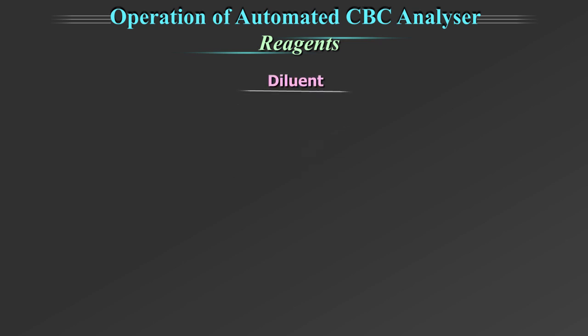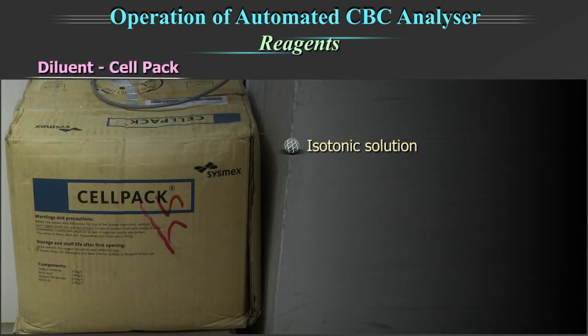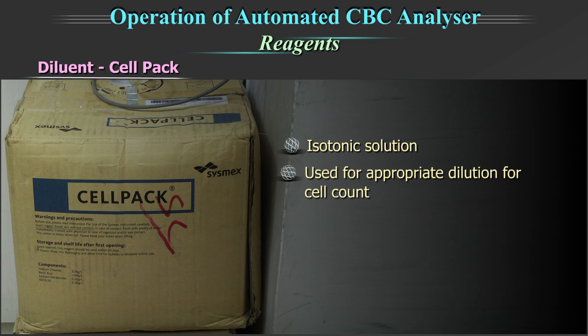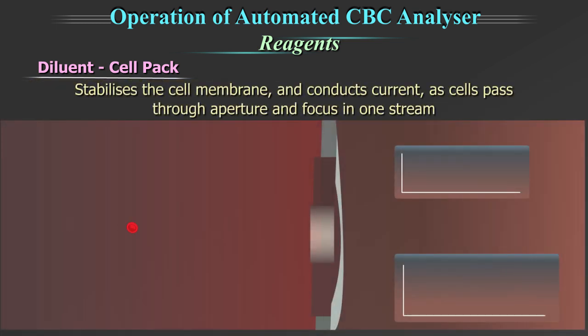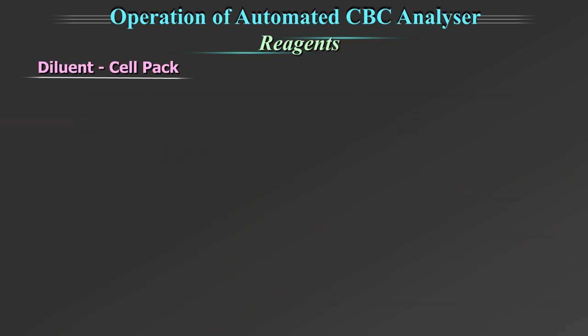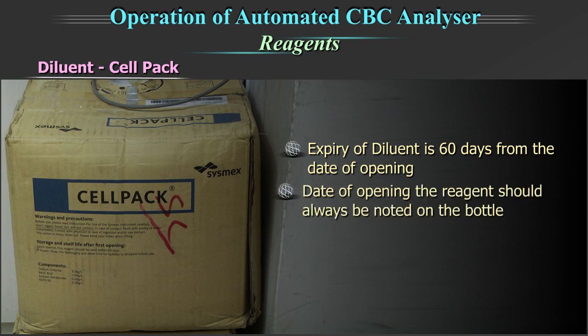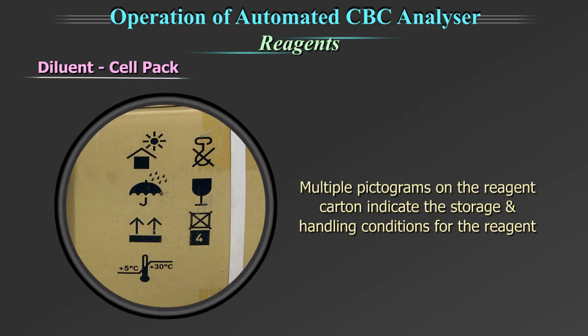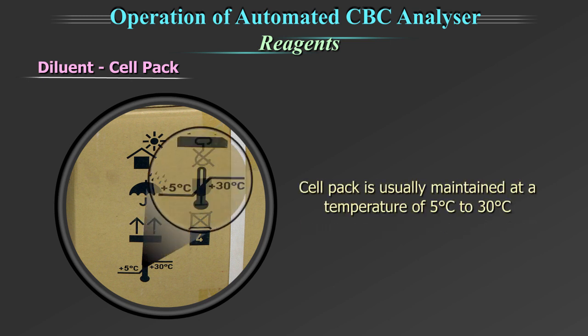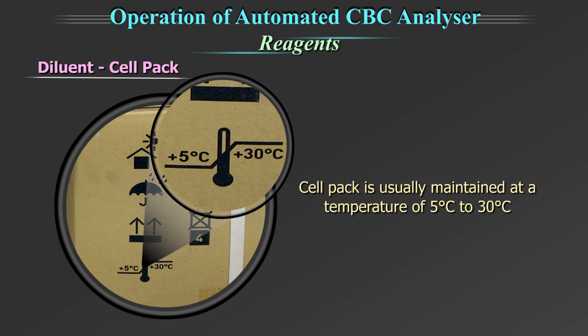The diluent — for example, cell pack — is an isotonic solution used for appropriate dilution for cell count. It stabilizes the cell membrane and conducts current as cells pass through the aperture and focus in one stream. The expiry of the diluent is 60 days from the date of opening. The date of opening should always be noted on the bottle. Multiple pictograms on the reagent carton indicate storage and handling conditions. The cell pack is usually maintained at a temperature of 5 to 30 degrees centigrade.